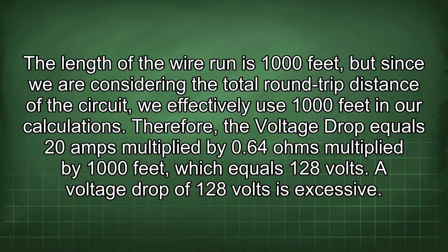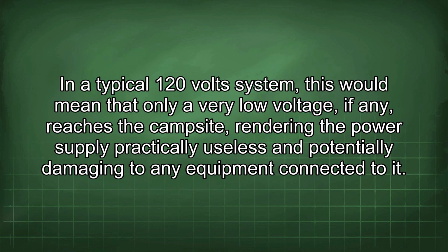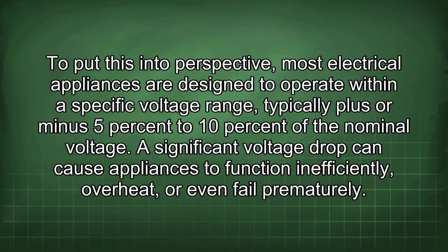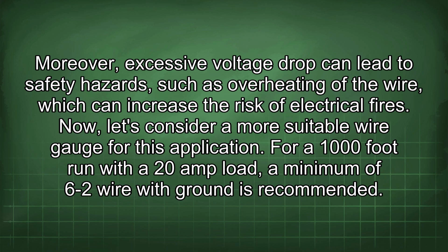A voltage drop of 128 volts is excessive. In a typical 120 volt system, this would mean that only a very low voltage, if any, reaches the campsite, rendering the power supply practically useless and potentially damaging to any equipment connected to it. To put this into perspective, most electrical appliances are designed to operate within a specific voltage range, typically plus or minus 5% to 10% of the nominal voltage. A significant voltage drop can cause appliances to function inefficiently, overheat, or even fail prematurely. Moreover, excessive voltage drop can lead to safety hazards, such as overheating of the wire, which can increase the risk of electrical fires.